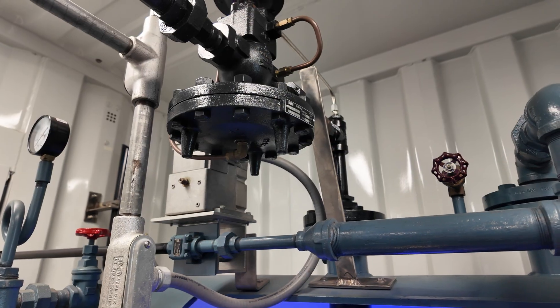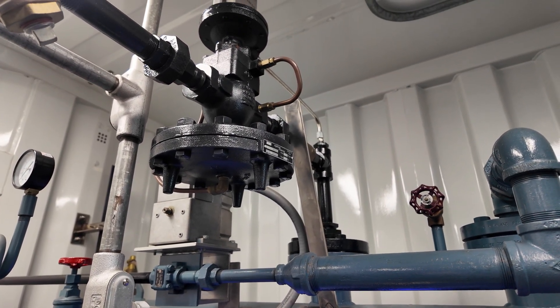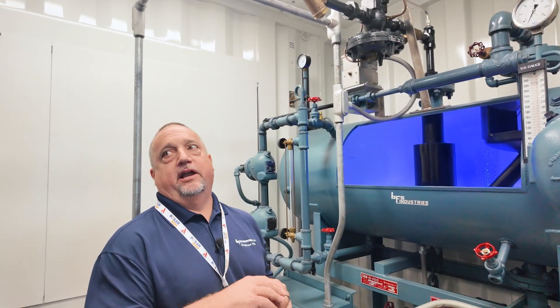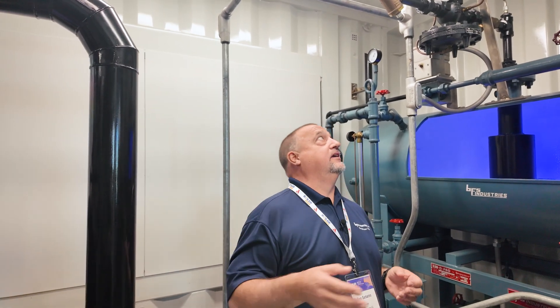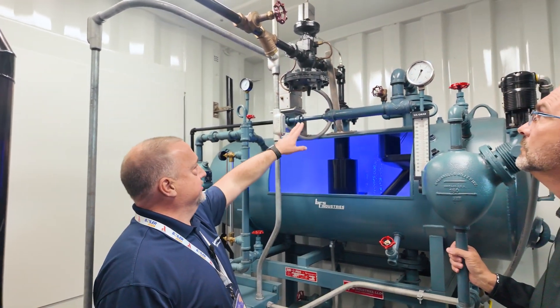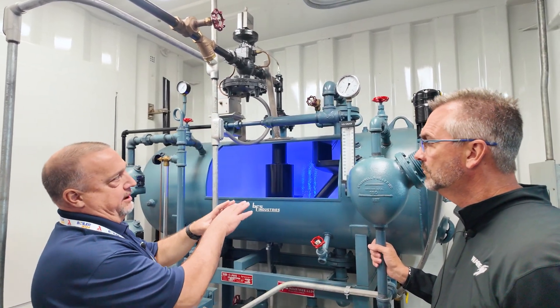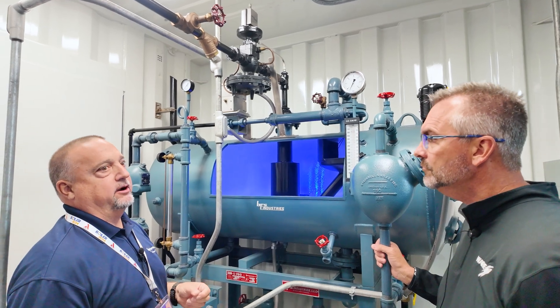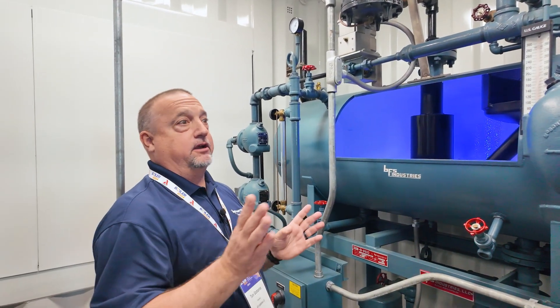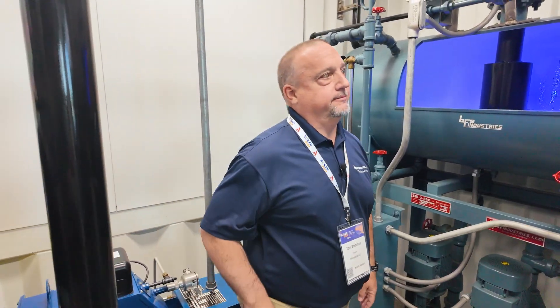This steam pressure reducing valve is very key, because we want the tank to operate at a positive pressure to drive the gases out to atmosphere. Typical operating pressure is 5 psi. The boiler might be operating at 125 psi, so we need a reducing valve to take that down to tank operating pressure. There's a sensing line that runs from the pilot on the PRV to the tank. When you spray cold water into that steam environment you start dropping pressure because you're collapsing the steam. The pilot senses this, opens the valve to bring in more steam, and brings it back to 5 psi, then shuts off.